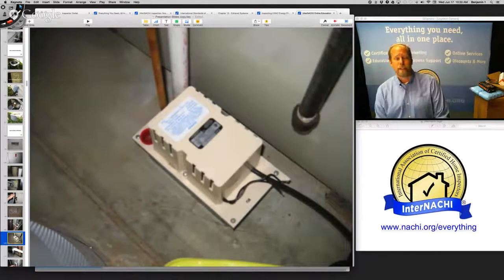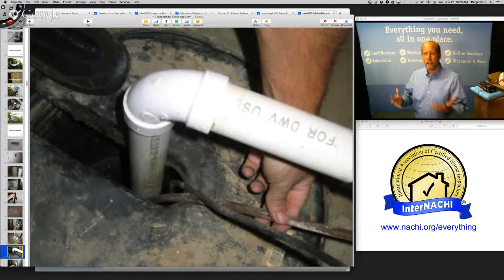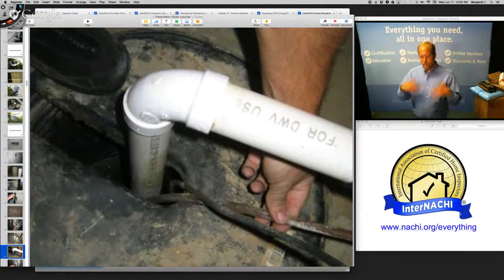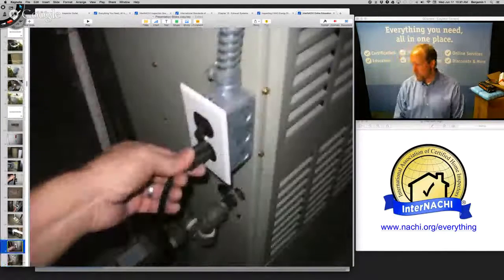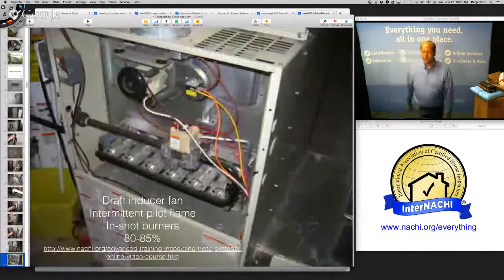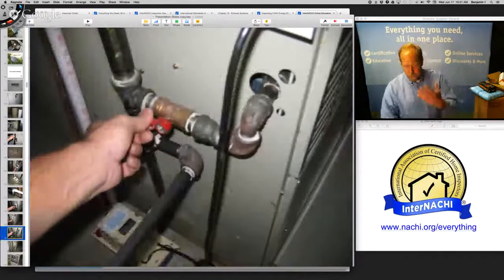The air conditioner evaporator coil — the fins should be relatively clean, it should be draining properly, and it should have a trap. It's missing a trap; it goes into a condensate pump, which discharges into a sump pump. We saw the sump pump discharge pipe on the outside with a clean-out fitting. This is how you have to think: a house is a system of interdependent parts. One part affects all others — that's how air conditioning gets connected to the sump pump.